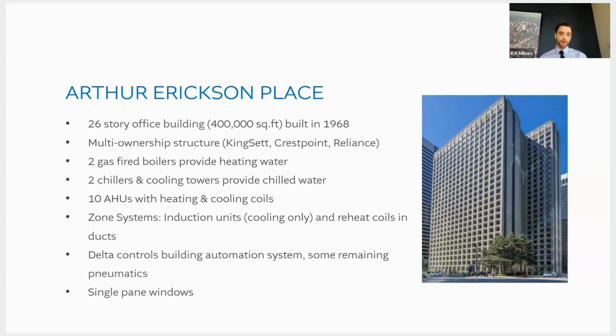For this building, it's a very traditional standard building, with gas and electricity for its energy makeup. It had gas-fired boilers, air handling units for heating and cooling, 2 chillers and cooling towers. It was zone systems, with induction units for cooling only.